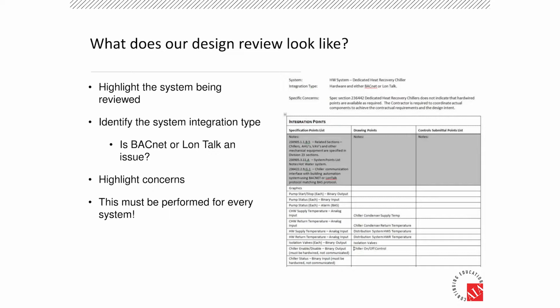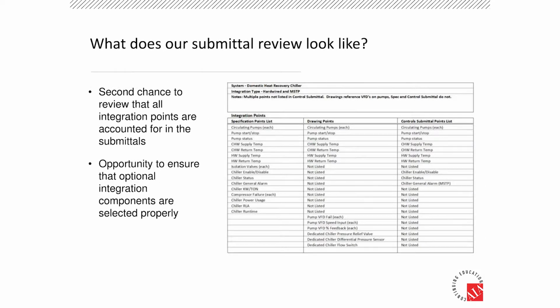We get a second chance when the submittals start coming through. If I have a specification points list, that always lives there, though you don't always have that. It might be something that comes just from the drawings only. You can see I have a lot of things here that just say not listed over and over again on the drawings and in the controls submittal that came through. It's an easy visual reference to look across and say, all right, we have something required in the spec, it wasn't in the drawings, and now it's not in the control submittal. Well, let's get on the same page. What's required? Let's get these points in. Let's see where we're at.